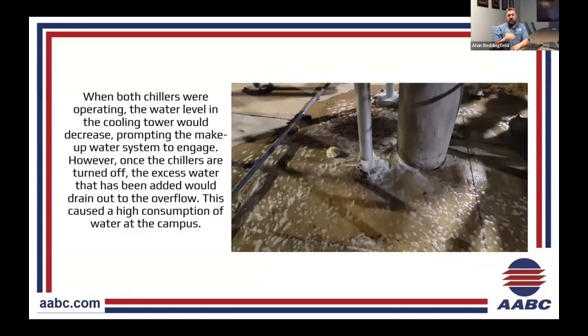Once the tower level dropped, the makeup would keep filling. Basically every single night, once you ran all day and it would fill up, once the tower would turn off, it would drain into the parking lot and level it back out, to the point where the district was just constantly dumping in water. And this was occurring at two separate projects.